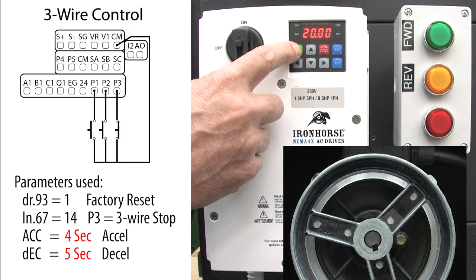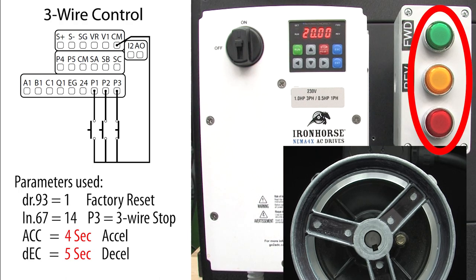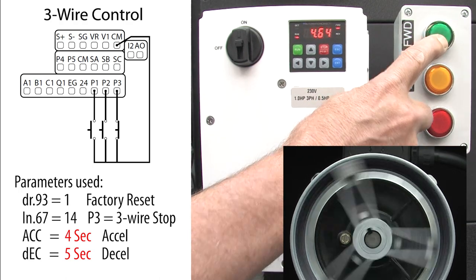Hit run. Nothing. Exactly what we expect because we told the drive to use these push buttons for control. Press the forward push button and yep, we ramp up to 20 Hz in the forward direction.